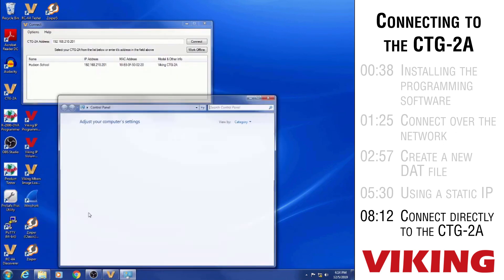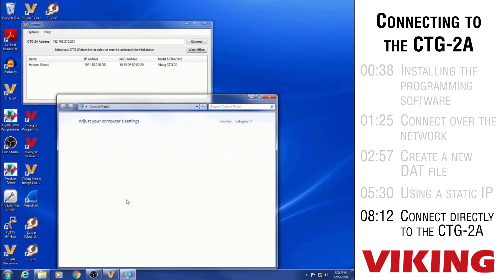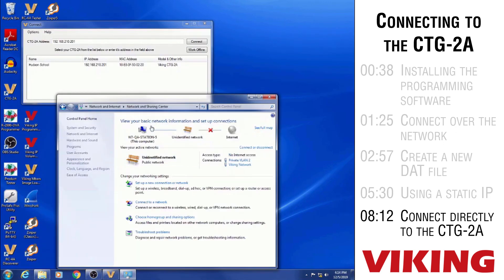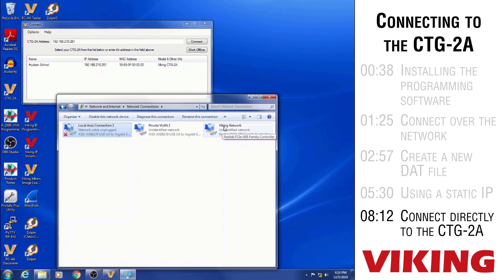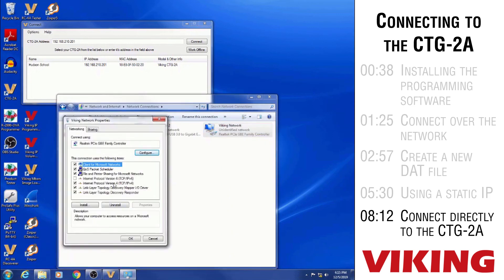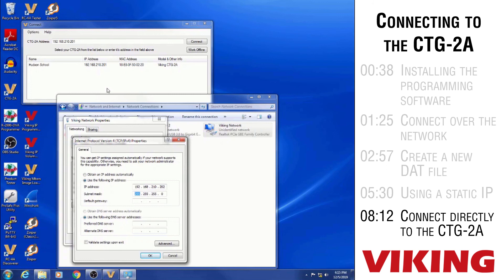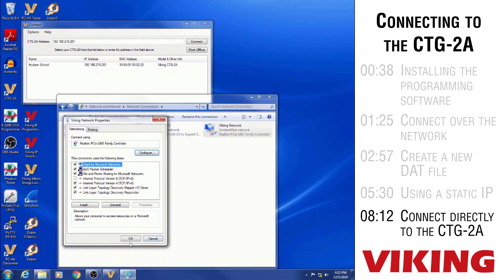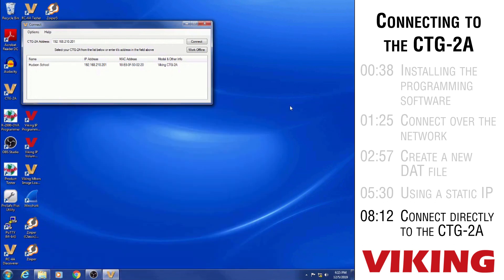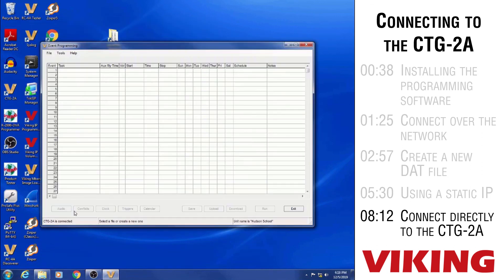So I want to go to control panel and network settings. And then I want to change the properties of this network card on the computer, go to the properties of that network card. Internet protocol 4. You can see how currently it's set to obtain an IP address automatically. So I'm going to give it a fixed IP address that's one number off from the IP address of the CTG-2A. I'll click OK or I hit tab and that filled in the subnet mask of 255.255.255.0. Then I can close all these network settings pages. We're able to successfully connect to it.